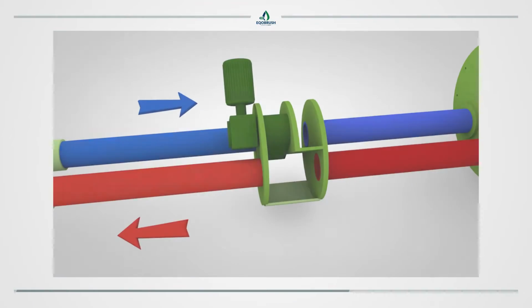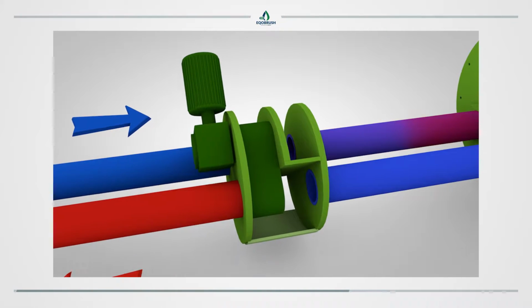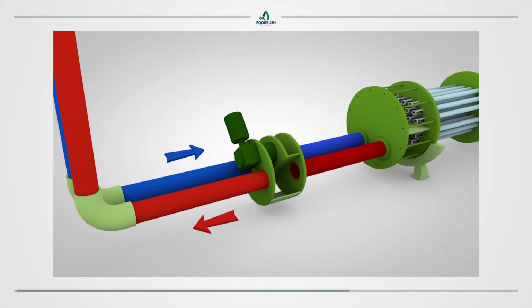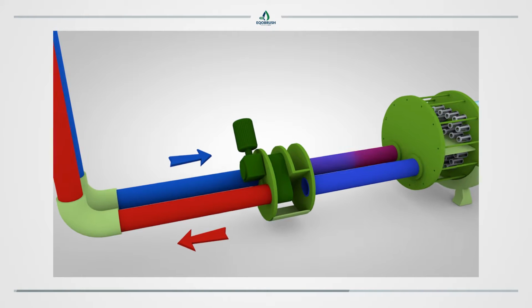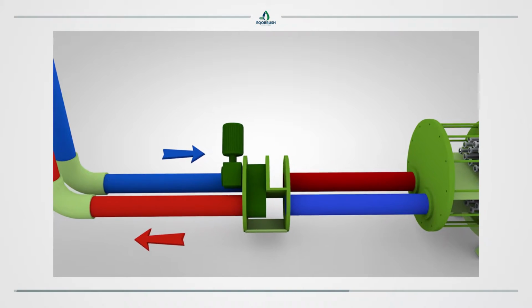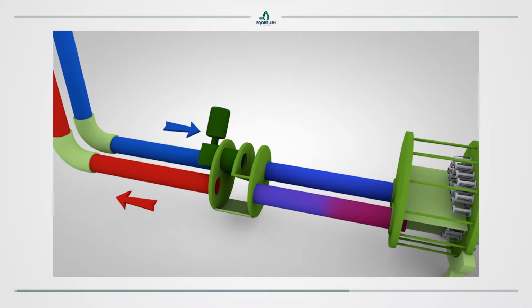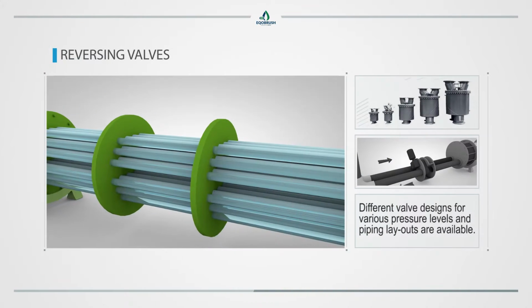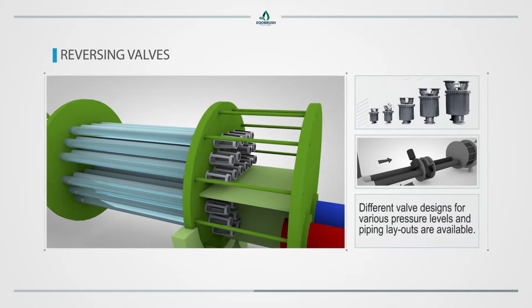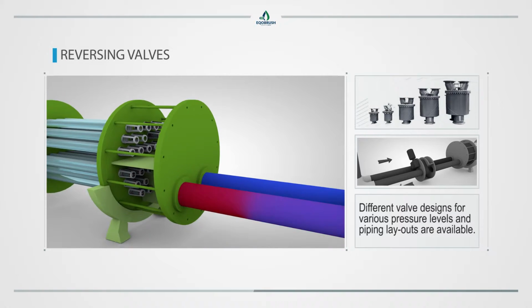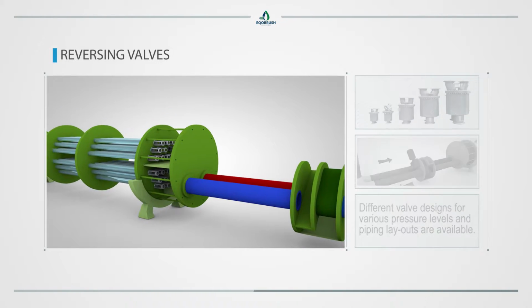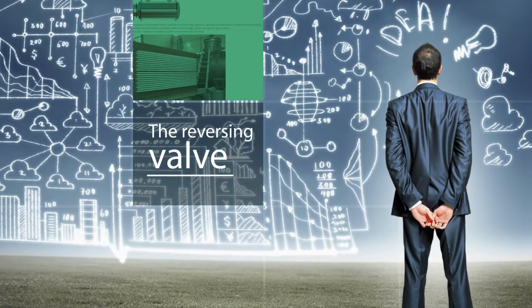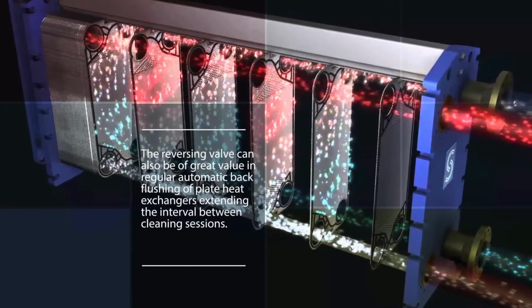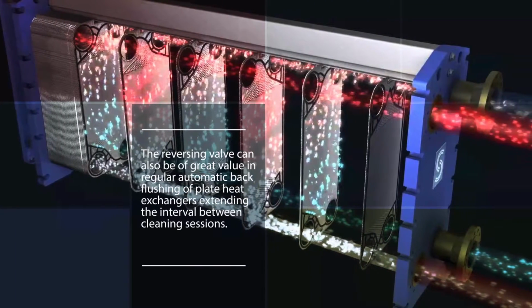Reversing valves with electrical actuators. Eqobrush valves are designed with a close to zero crossover rate. Crossover is the leaking of hot water into the cold water stream, which negatively affects the process performance. Different valve designs for different pressure levels and piping layouts are available. The reversing valve can also be of great value in regular automatic backflushing of plate heat exchangers, extending the interval between cleaning sessions.